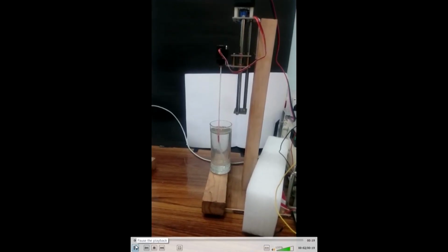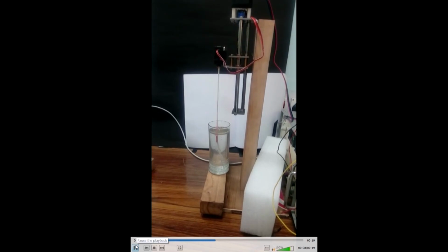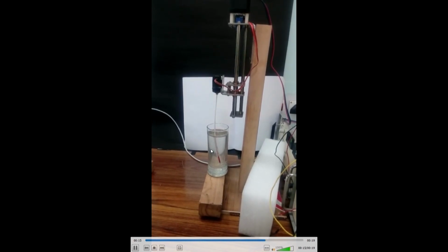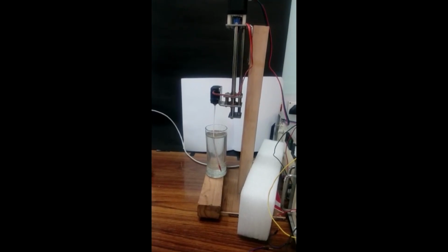With this strategy implemented on the real system, we have observed that the needling system can be inserted with the bevel tip, and the angle diversion from the plane, that is the line of insertion, is shown here. This video confirms that, due to integral sliding mode control with the super twisting algorithm, the needle lies within the desired plane of interest, with the bevel angle coming into the picture because of the tissue reaction force.